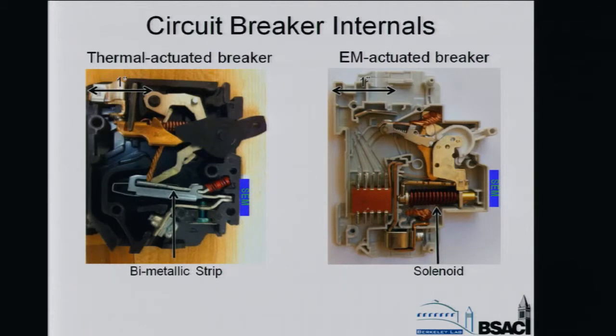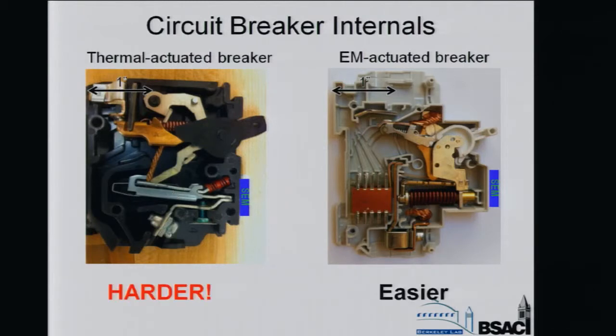On the right is an electromagnetic actuated breaker, which functions fundamentally differently. There's a solenoid in the breaker which concentrates the magnetic field by roughly 10 to 20x. When the current through the solenoid becomes large enough, that creates a large magnetic field, and the Lorentz force applied to this lever pulls it in and actuates the breaker. So you can imagine that in designing a sensor that measures the magnetic field around the breaker to sense the current, this solenoid would be very advantageous because it essentially relaxes the requirements on the SNR at the sensor.